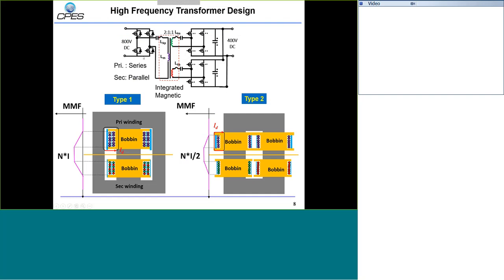The most important part of the design is the transformer. At high frequency, the transformer must have very small loss, and it must satisfy the insulation requirement for medium-voltage applications. Although the input terminal for the DC-DC converter is just 800 volt, we connect this terminal to the medium-voltage AC terminal, so we must ensure the insulation can satisfy the medium-voltage requirement. We need to select the transformer topology.